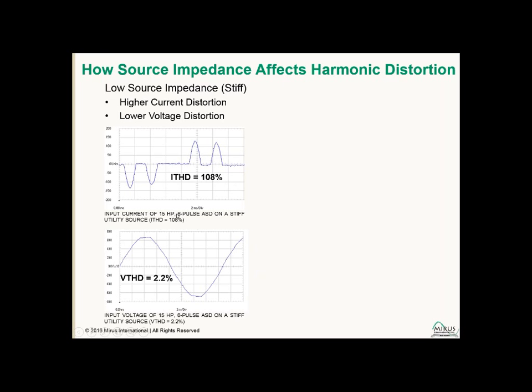So in this case, it's a 15 horsepower drive, a 6-pulse drive on a stiff source. The total harmonic current distortion is 108%. So it's got a high level of current distortion. But it's being fed by a stiff source, and therefore with low impedance, and therefore the voltage distortion that these current harmonics passing through the impedance creates is relatively low. So we only have 2.2%, hardly any distortion in the voltage.